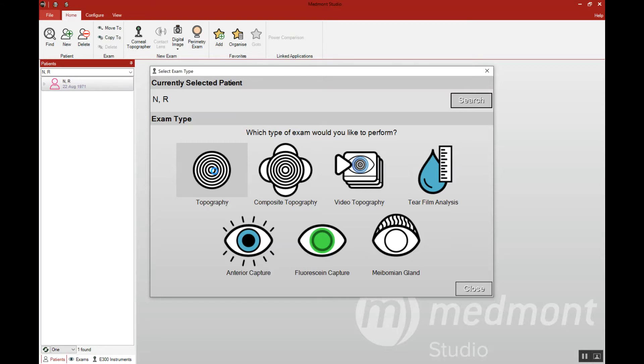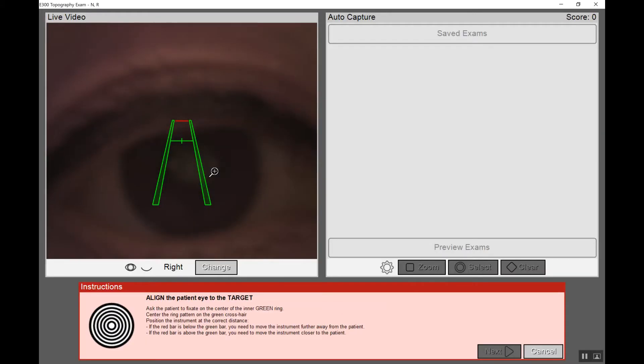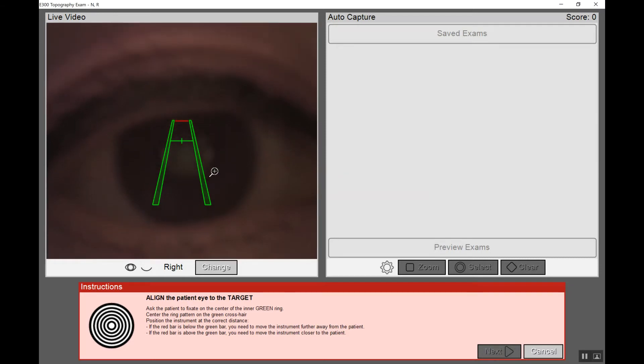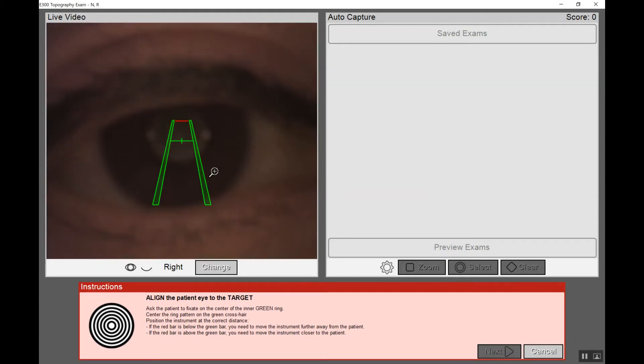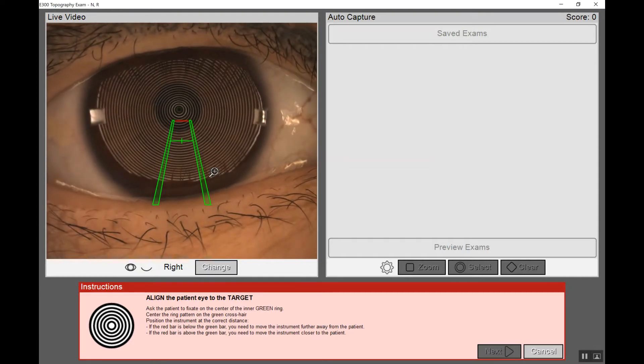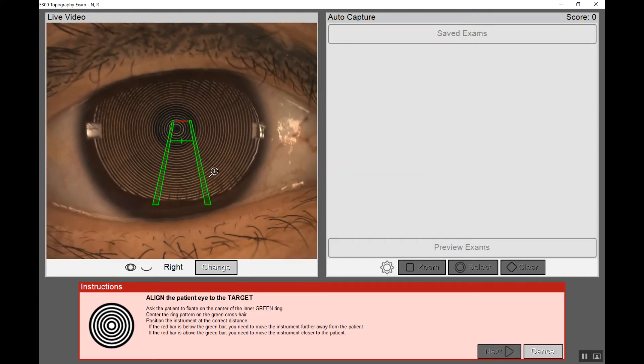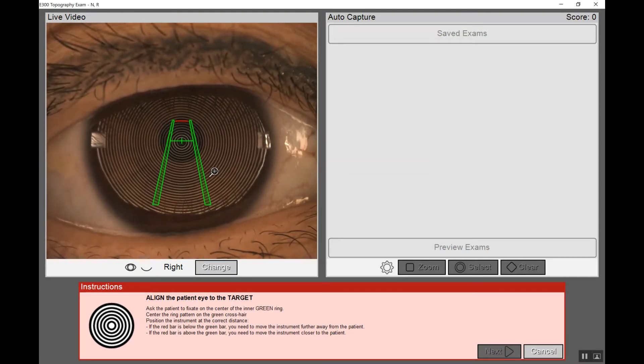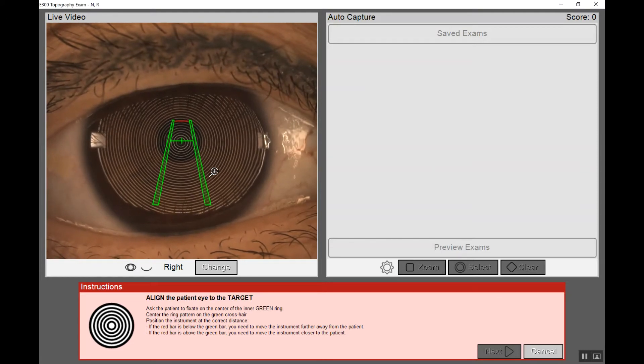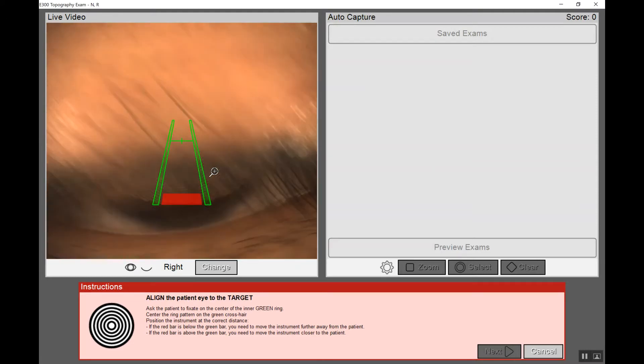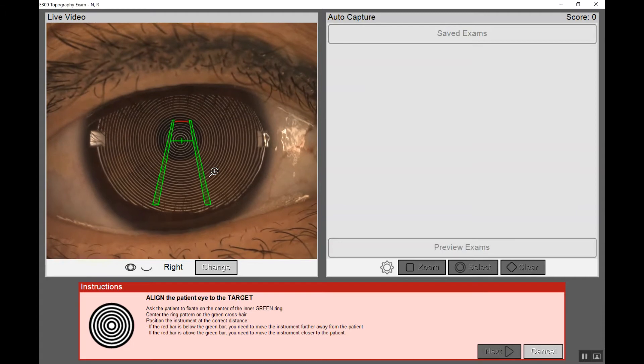When we select it, you may hear the wheel inside the instrument moving around, ensuring that it has the right focusing lens for the topography capture. Then it'll bring up the test window. What we're going to do is center the green crosshair to the central ring. If the rings aren't apparent, then move the instrument forward until you can begin to see them. Put that green crosshair on the center using the joystick and that focuses the axis of the instrument to the patient's visual axis.